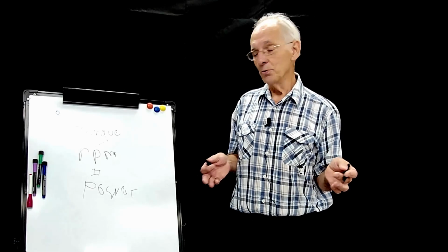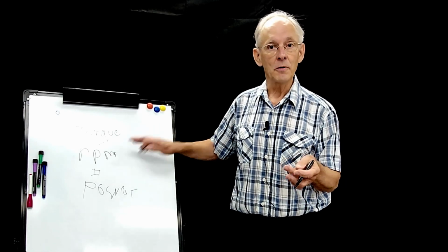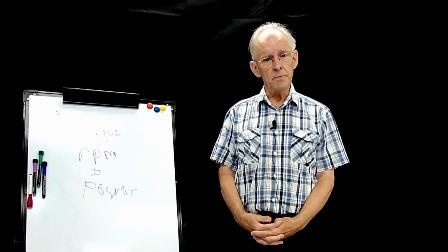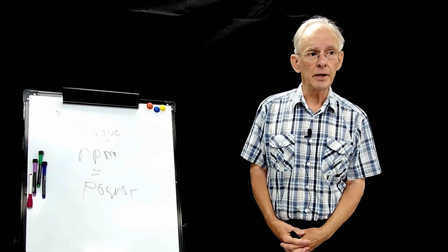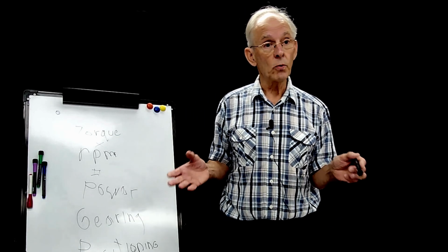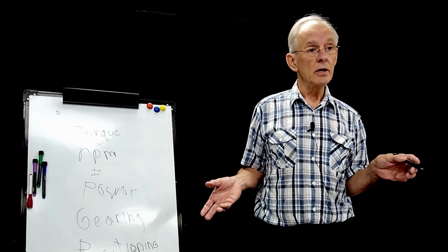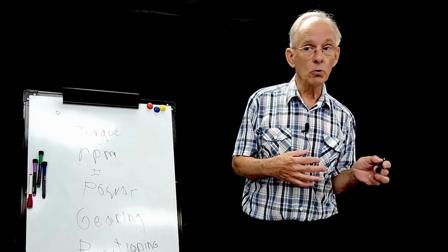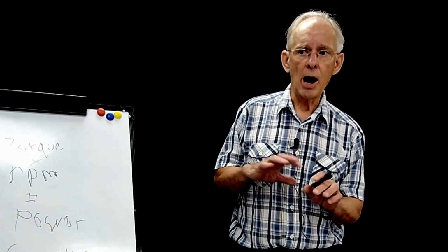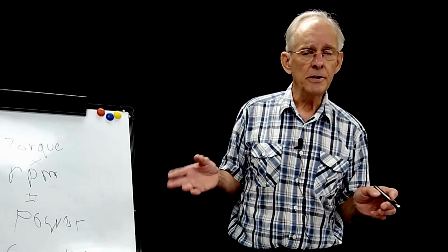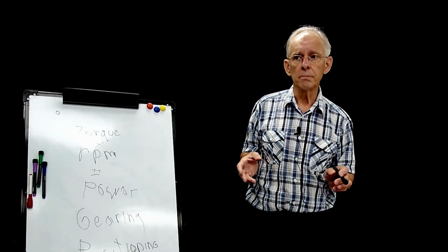When selecting a motor, you really want to know the torque and the RPMs. Decrease the speed by a ratio of 10 to 1, the torque also goes up by 10 to 1. Open loop is where there is no encoder feeding back to your controller the position. If you're going to run this thing 24/7 and you want to run it at some optimal speed, then a VFD on the AC motor is a much better choice.